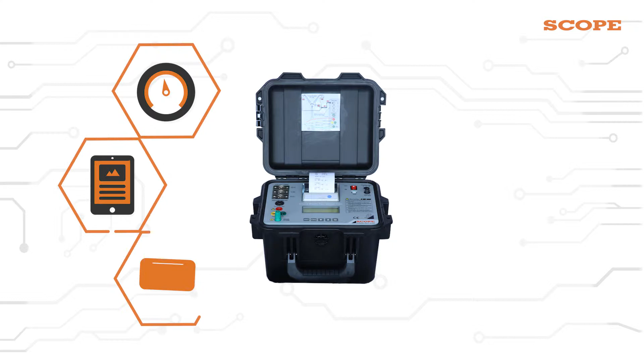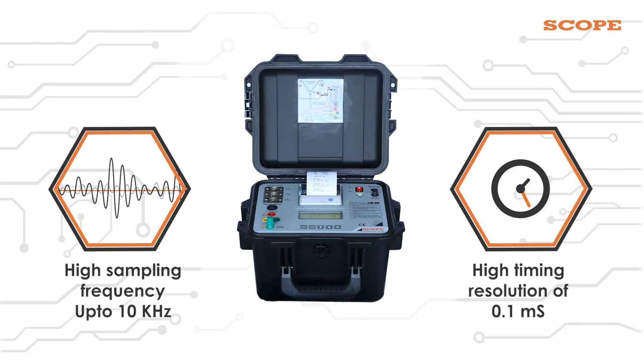One of the important parameters that define the proper operation of a circuit breaker is its timing of tripping, opening and closing of its contact. Scope MXP Plus measures, displays and prints close timing, open timing and close open timing of the circuit breaker. It has very high speed sampling frequency up to 10 kHz, which offers high timing resolution of 0.1 millisecond.